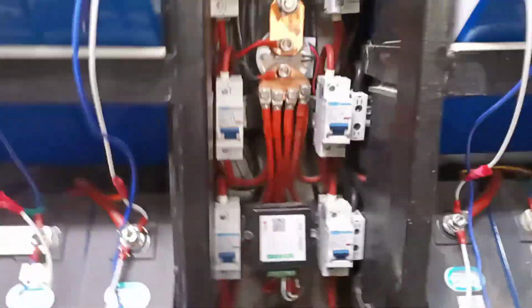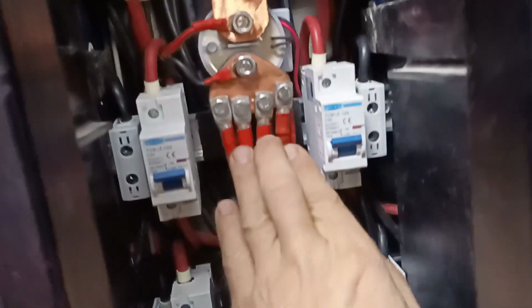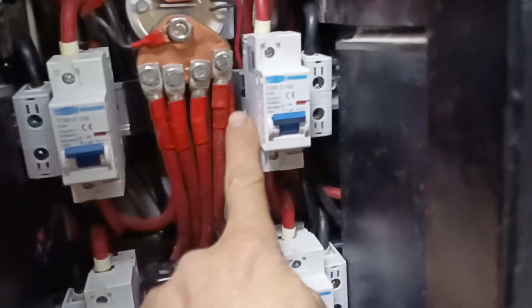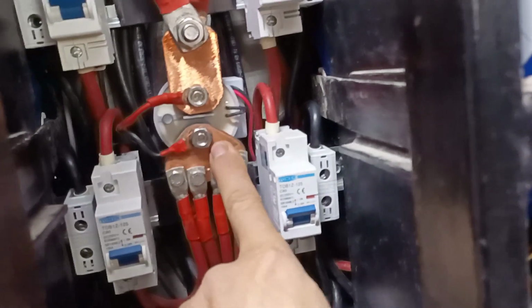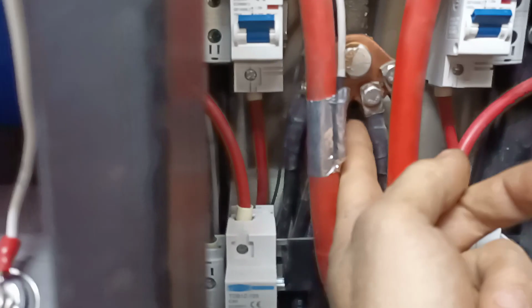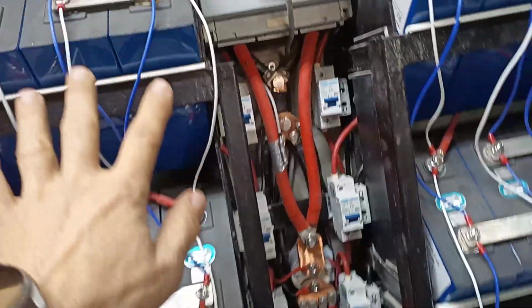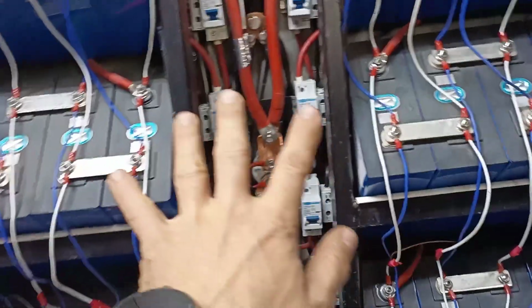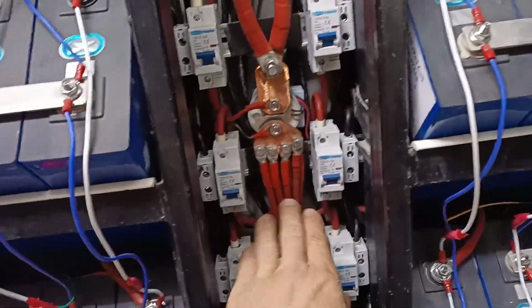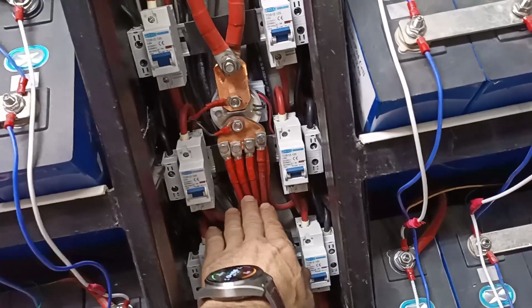Also, this cable links—let's say this negative is connected here, and all 8 banks, you can see 4 cables on top, but there are also 4 cables on the back on this copper plate. It's the same on the shunt side: 4 wires on top and 4 on the back, so all 8 banks receive the same length and the same wire.